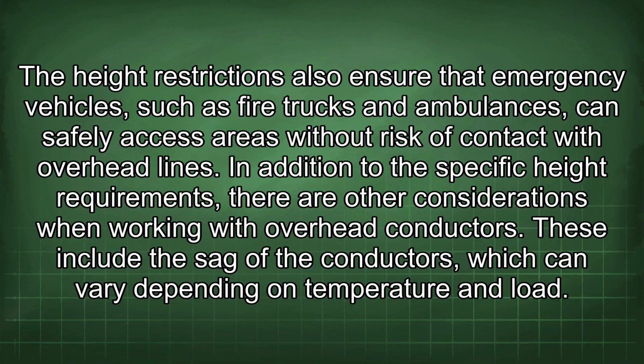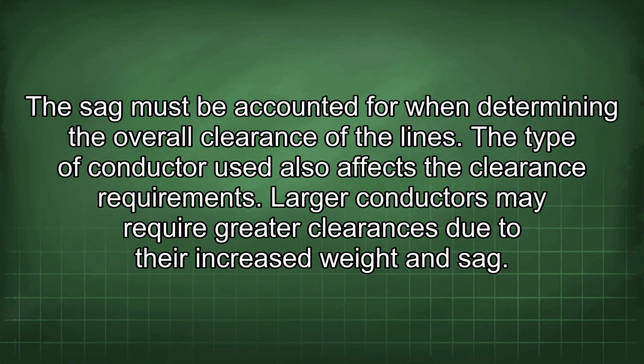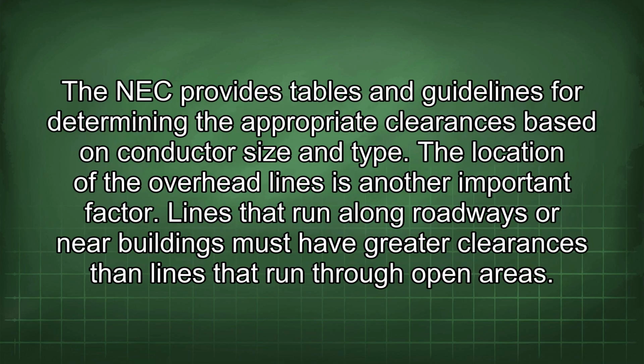In addition to the specific height requirements, there are other considerations when working with overhead conductors. These include the sag of the conductors, which can vary depending on temperature and load. The sag must be accounted for when determining the overall clearance of the lines. The type of conductor used also affects the clearance requirements. Larger conductors may require greater clearances due to their increased weight and sag. The NEC provides tables and guidelines for determining the appropriate clearances based on conductor size and type.